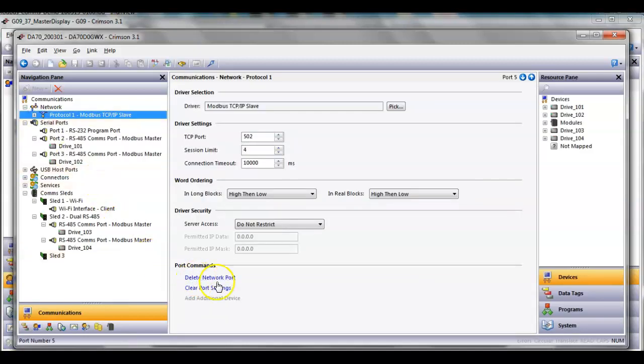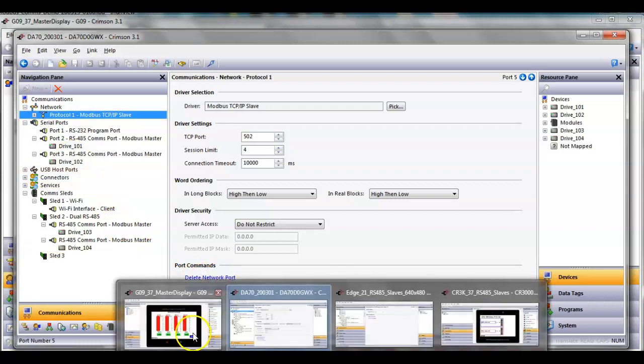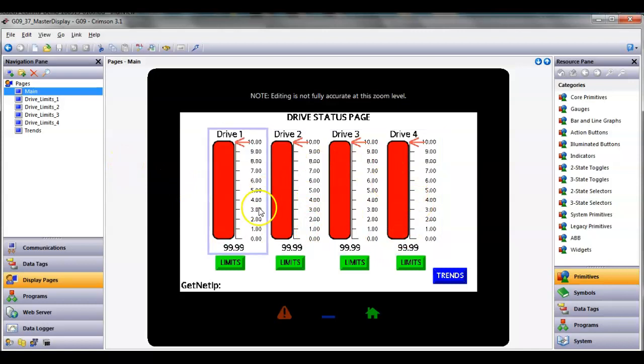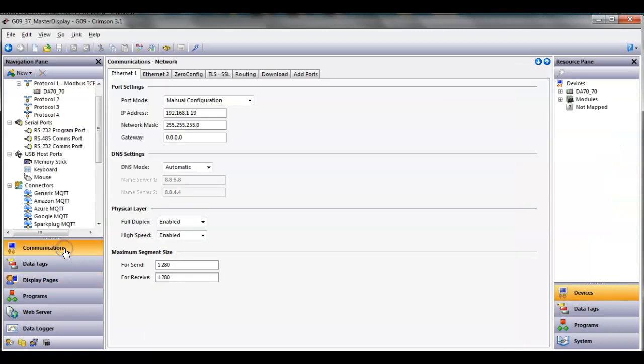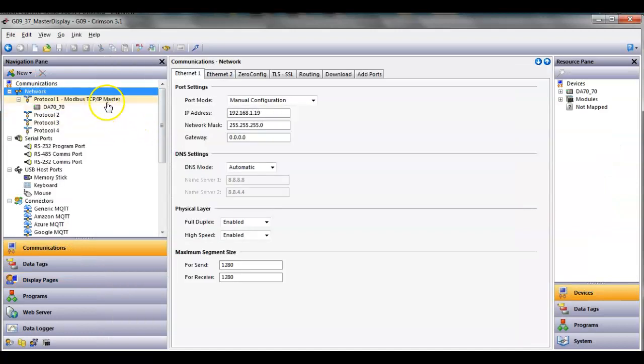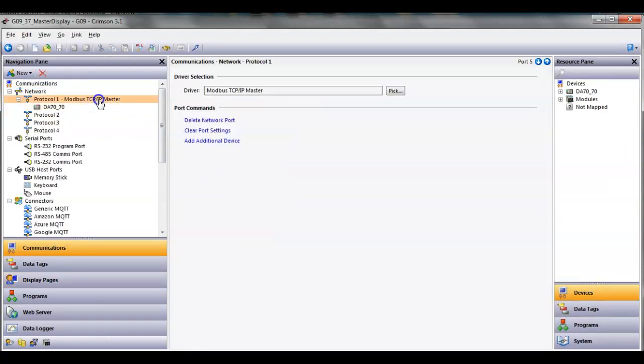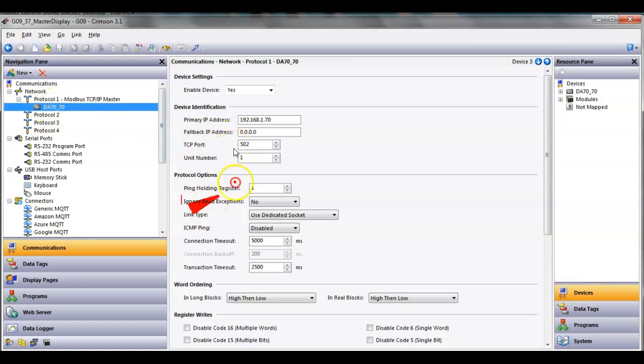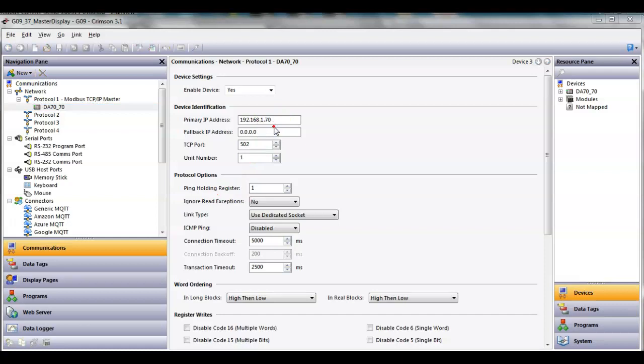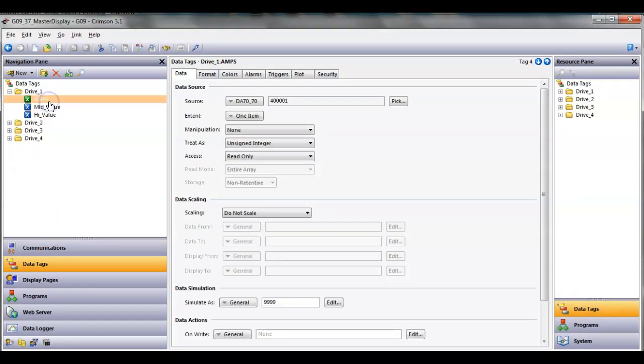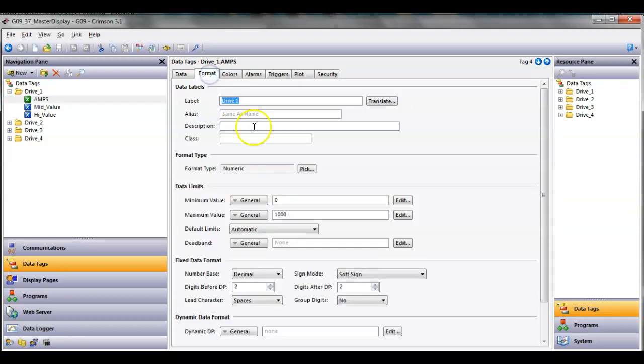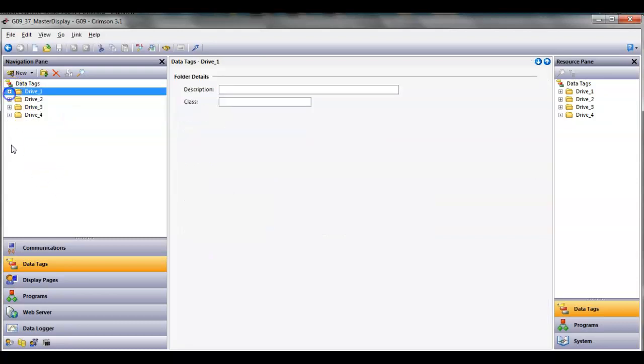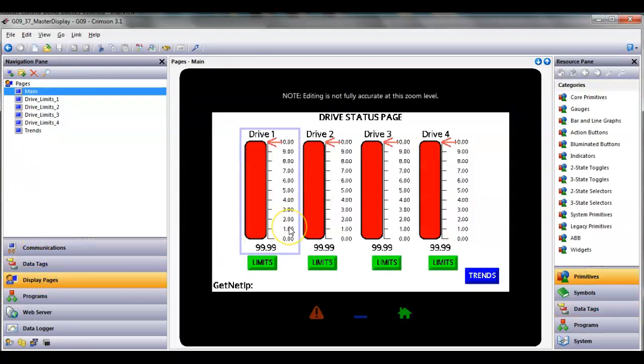Over at the main HMI, the G09 where I want the graphics, this is where I have that coming in. This guy is set up as a Modbus master, and it's going to be pulling the DA-70. This is the actual IP address of the edge. If I go to data tags, I've created some folders. I've got a tag here called amps. I'm mapping it to the register. I've done some things under formatting and also done some things under coloring that's going to be kind of cool to look at.